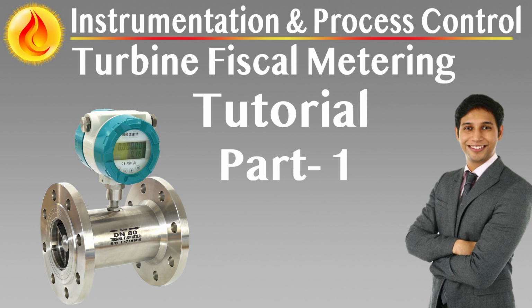Backup microcomputers and non-resettable mechanical counters ensure that a single electronic failure does not compromise data integrity. Redundancy allows uninterrupted operation during maintenance, calibration, or unexpected faults, essential for facilities where flow interruptions equate to contractual penalties or safety risks.